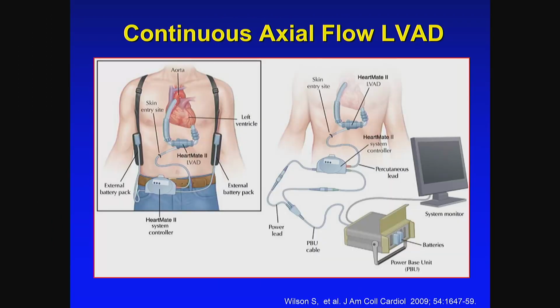And so the engineers continued to innovate by developing the continuous axial flow LVAD known as the HeartMate 2. Rather than having an electrically driven pusher plate, here was a rotor that was turning between 9,000 and 10,000 revolutions per minute. This was a valveless pump that ensured unidirectional flow with this electrically driven rotor. Blood gets sucked out of the apex of the left heart, accelerated through the housing of the pump and through the outflow cannula to the aorta.